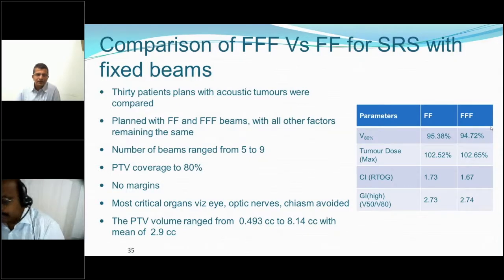And I have seen some hospitals take the monitor chamber output and use that as the reference because they cannot place another chamber there. You can even take the monitor chamber output and use it as your reference chamber for your verification. So that is also one possibility. When I used small collimators, cones for radiosurgery, I used to keep the ion chamber between the cones and the primary, because the primary is a little larger than the cone. So I used to put it there in between. It is a difficult thing when you want to do it for very small field sizes. Keeping another chamber in the path of the beam is a difficult thing.